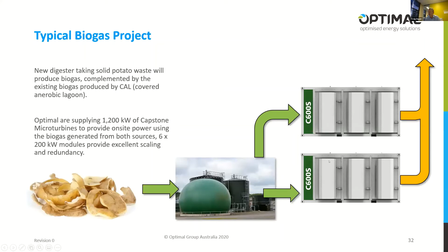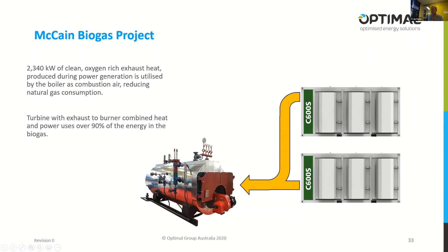The waste heat from those turbines, the exhaust, we then direct into their existing MaxiTherm 25 megawatt steam boiler. We're going to put a Saacke high temperature, hot air fired burner into that boiler, so all of our exhaust will be used as combustion air in the boiler. That reduces the natural gas load on that boiler by 20%, and obviously delivers further greenhouse gas reductions to the customer. So, as I said, McCain's intend to go to zero emissions.